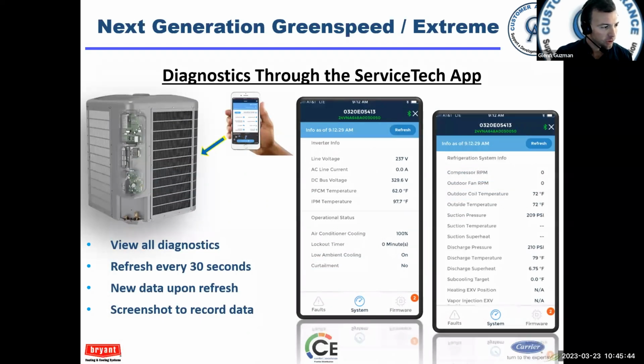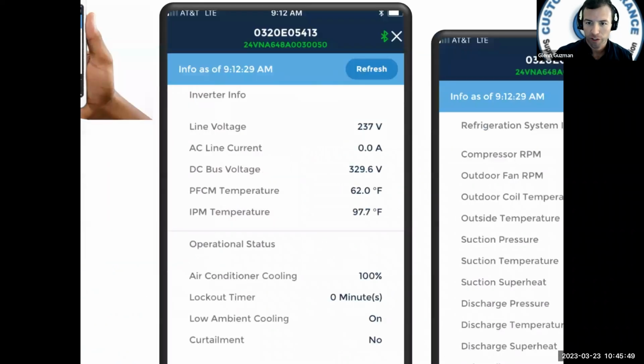Here's some more pictures of what you'll see, and I'll zoom in so you guys can read it better. At the top, model and serial number, so you know which unit you're connected to. Line voltage, AC line current, DC bus voltage, all that's there. This PFCM and IPM temperature—these are some internal temperature sensors in the VFD.